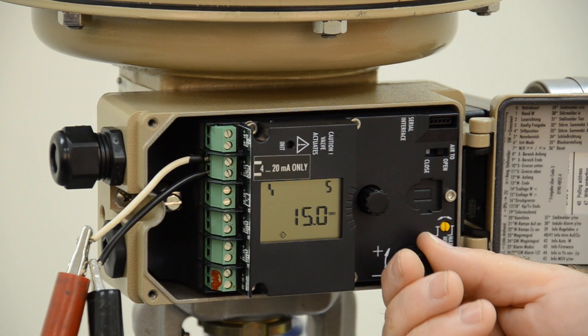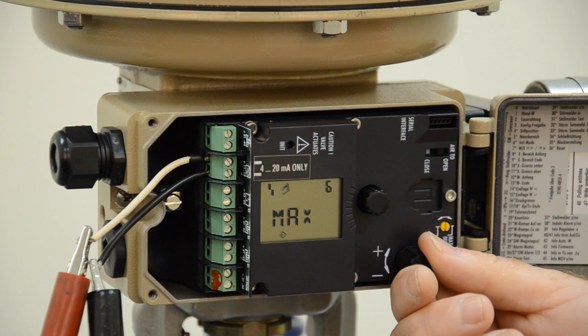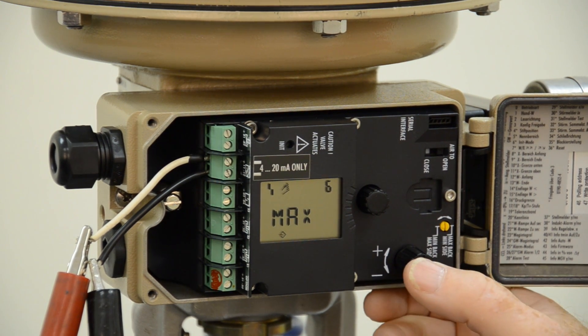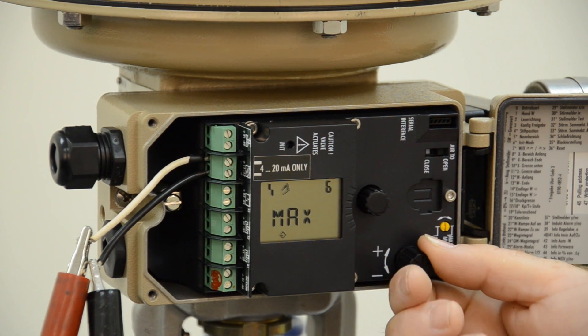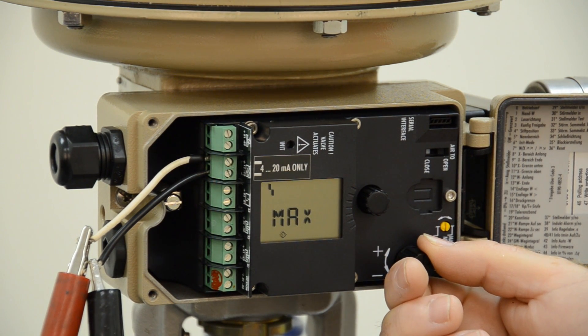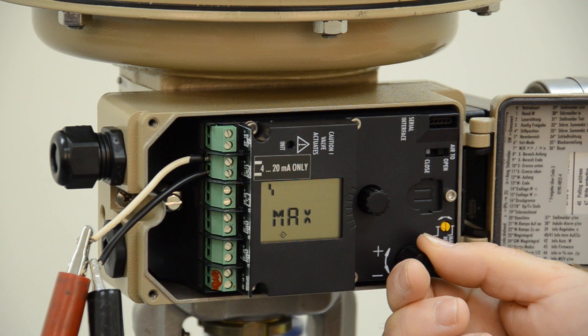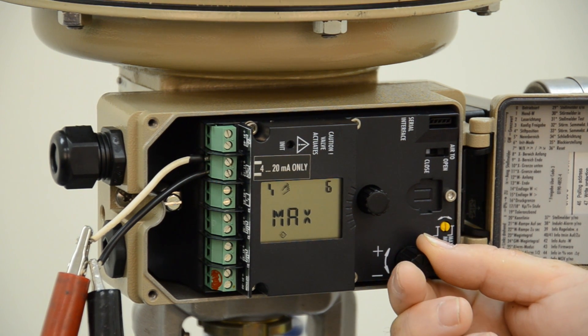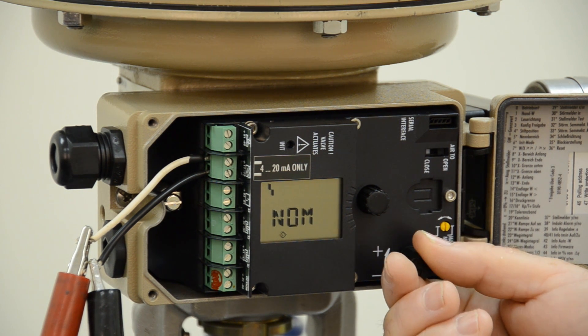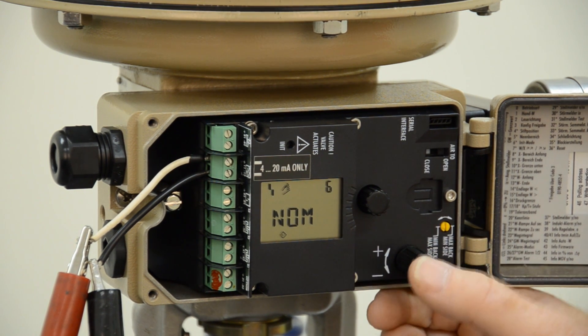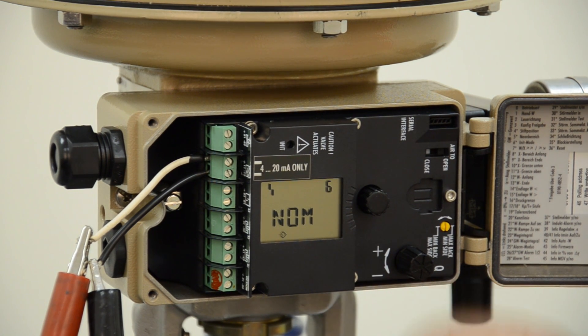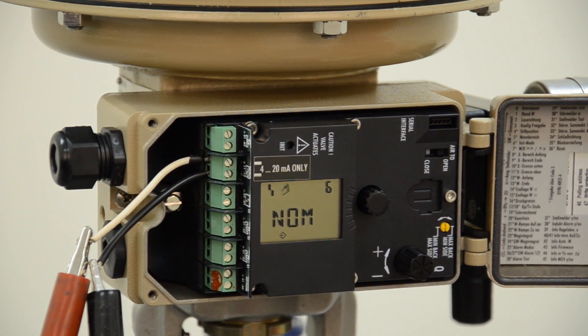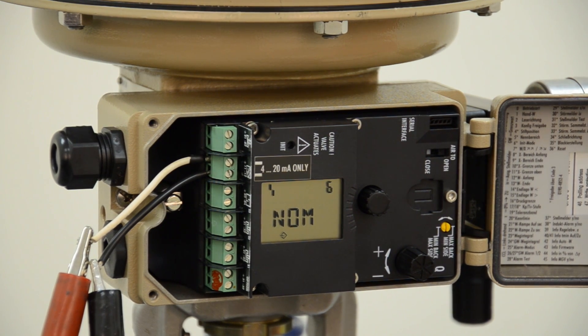Our next code is code 6. We press code 6. This is the travel distance that we want the actuator. And we've set it up for 15 millimeters, which is going to be in this case, we set under nominal travel. We press again to acknowledge. And at this point, we've done all the configuration that we need.